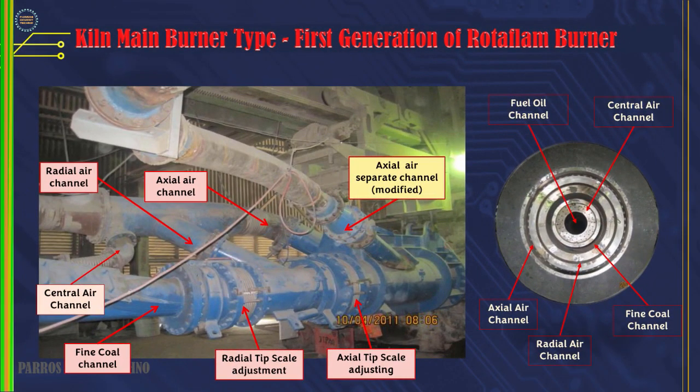This is a picture of the first generation Rotaflam burner. It has axial air, radial air, and central air channels, a coal fuel line, and a scale to change the position of the burner nozzle. Each air line from the primary fan is equipped with a valve to open and close, except for the coal fuel line which has no valve installed. The maximum primary air pressure for the primary fan is around 220 millibar, and modifications can be made by adding a roots blower to drain the axial air separately.